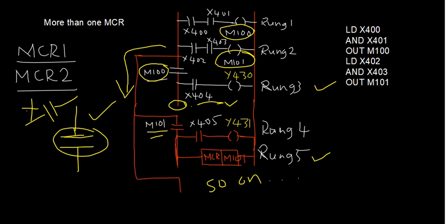Now the next instruction must be related to M100, which is located in the power rail. As you can see, the instruction for this is MC M100. This is a very important point to be noted, MC M100. So what does that mean? You are setting the master control relay coil now, and after that whatever you have is again simple.